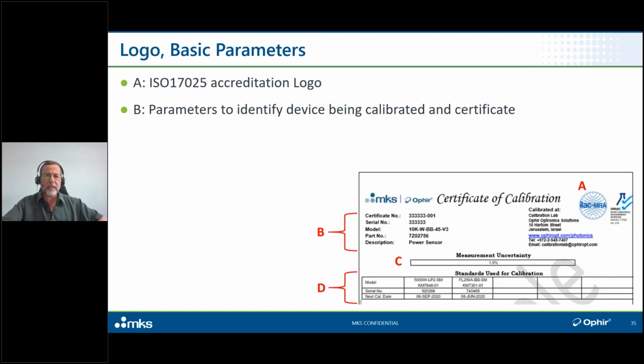Certain power ranges, certain whatever it is, are outside the scope. Very few, but there are some. And so in this case, it's the Israel Laboratory Accreditation Authority in our calibration facility in Germany, in the US, and in Japan, it'll be the relevant logo of the standards body that certified each particular facility. B, okay, those are the parameters to identify the device being calibrated, the serial number of the sensor, the model number and its name, the description, and also the certificate number if this is the third certificate being issued for that serial number that'll show up that'll be stated there as well.